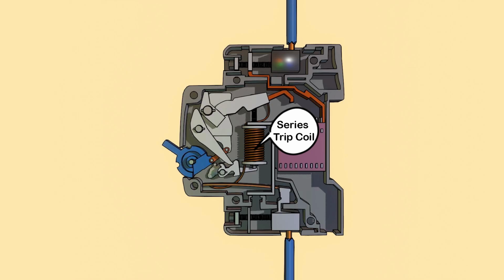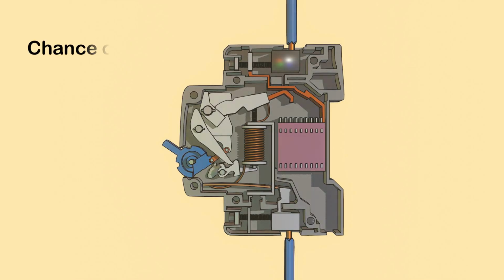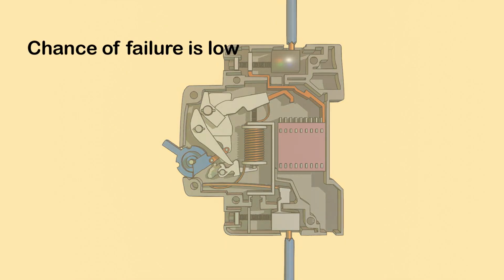It has several advantages. Since the coil is powered by the main circuit, the chance of failure is less than with a shunt trip coil. In shunt trip coils, external power is required. If that power fails, tripping may not occur. But in series trip, this does not happen. A shunt trip mechanism needs a separate supply and current transformers, and these make the system complex and require more space. But in series trip, the arrangement is inside the circuit breaker.